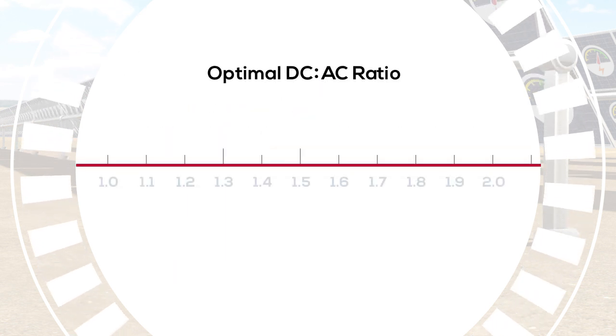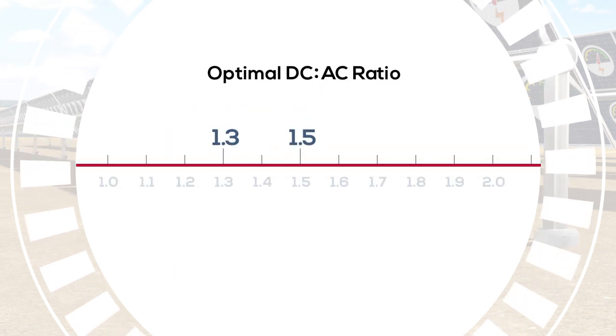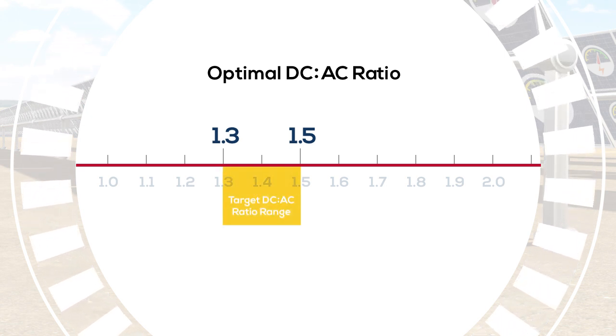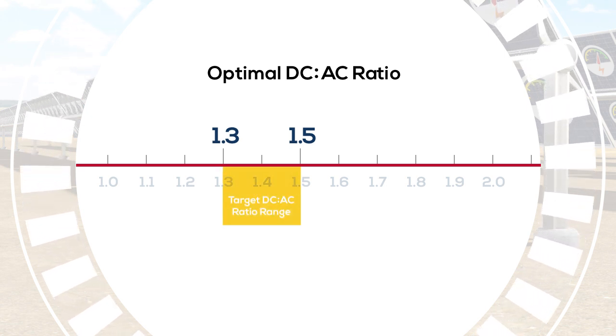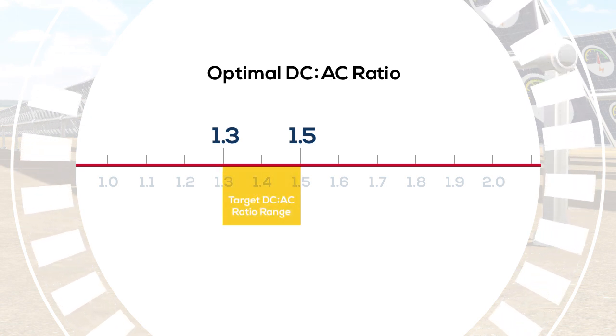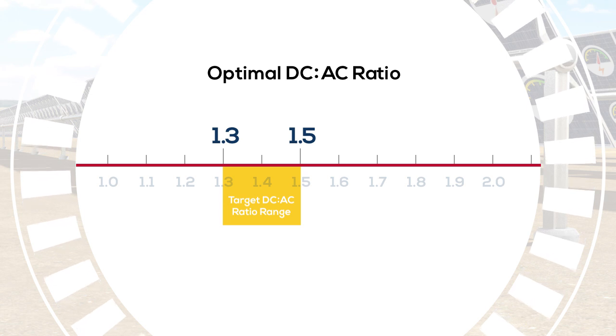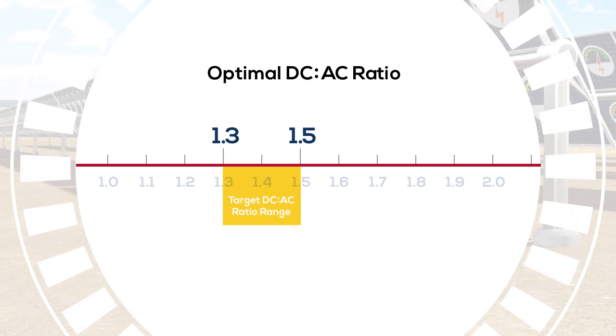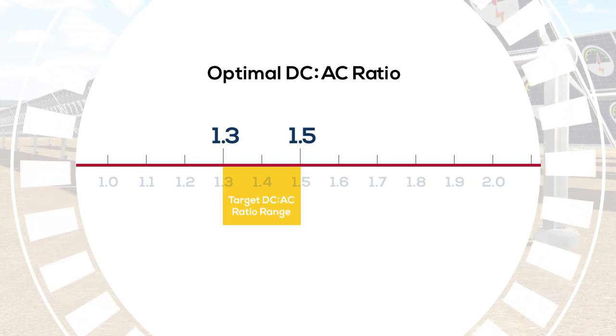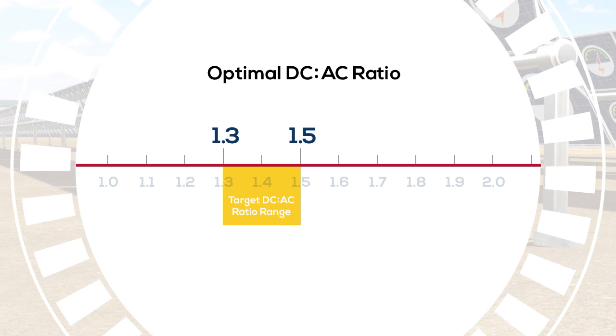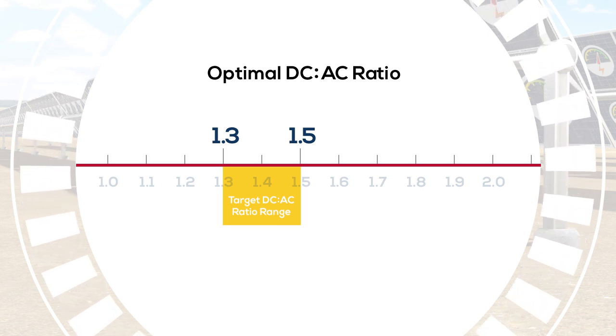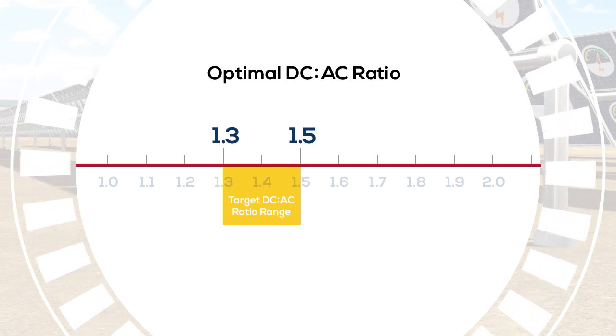Generally, you want a DC to AC ratio of at least 1.3, sometimes as high as 1.5, to maximize production and minimize the levelized cost of electricity for your project. But some inverters won't allow you to get into that target DC to AC ratio range.